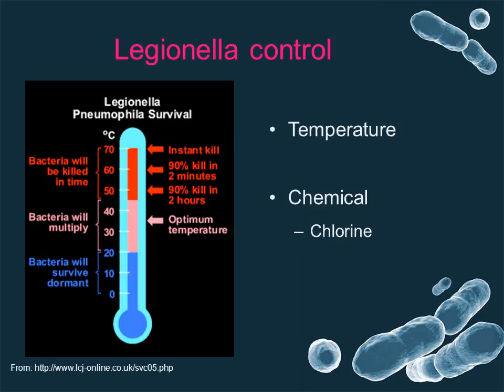Legionella can be controlled in water via two main methods. The first is via temperature. The bacteria has an optimum temperature between 20 and 45 degrees. Below 20 degrees, the bacteria survives but remains dormant. Above about 45 degrees, the bacteria will be killed, and at 70 degrees, the bacteria is killed instantly. There are several chemicals that can be used to control Legionella, and these include chlorine-based biocides.